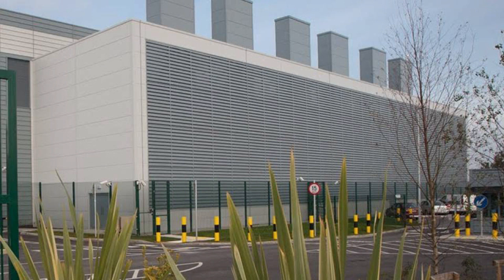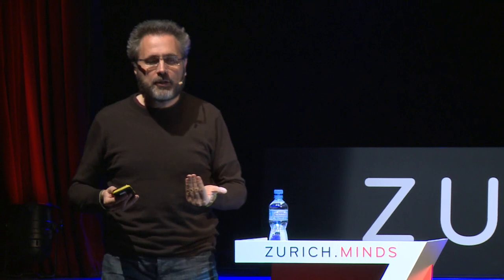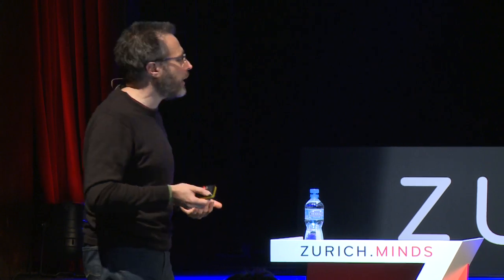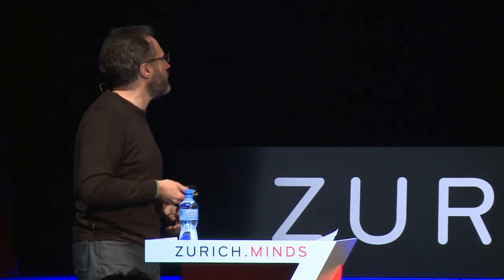And you notice that in no place here did I mention refrigeration, right, or chillers. So most of our data centers don't have mechanical refrigeration, big chillers that consume a lot of energy, because if you use this so-called free cooling or environmental cooling, then that's just plenty.